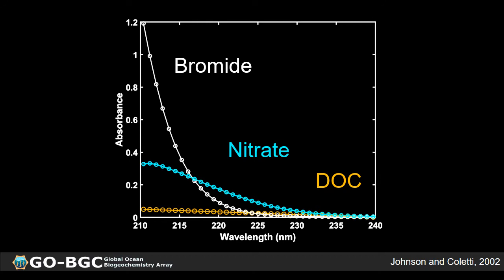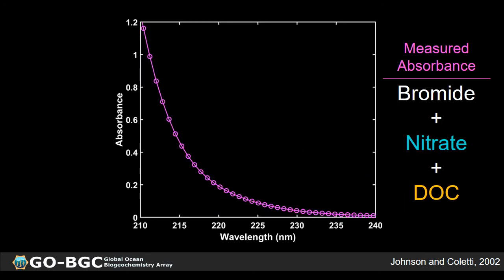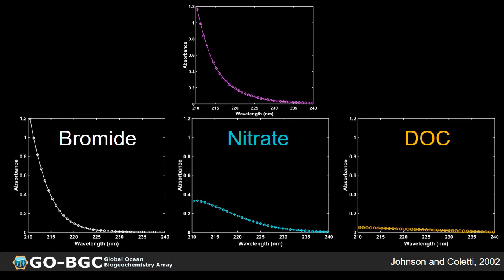So when you actually measure the absorbance of seawater, it's the sum of these three components, which is shown in pink here: bromide, nitrate, and the linear contribution from DOC. The challenge really is how to separate, or deconvolute, these three components from the overall measured absorbance. If you measure this absorbance, how do you break it apart into the three components that contribute to it: bromide, nitrate, and DOC? The initial algorithms that were tested tried to simultaneously fit all three spectra to the measured absorbance. This worked well most of the time, but sometimes it led to overfitting or overcompensation of certain spectra and led to negative nitrate concentrations, which we know is not possible.